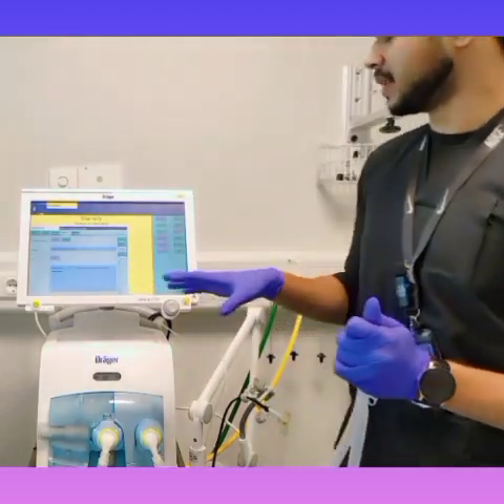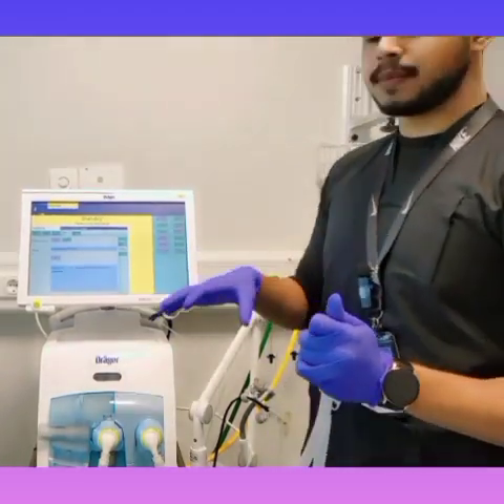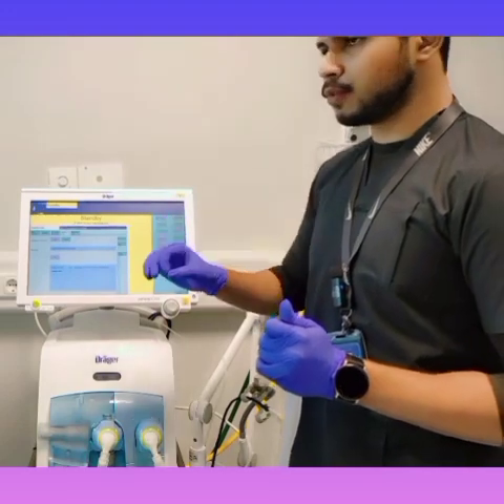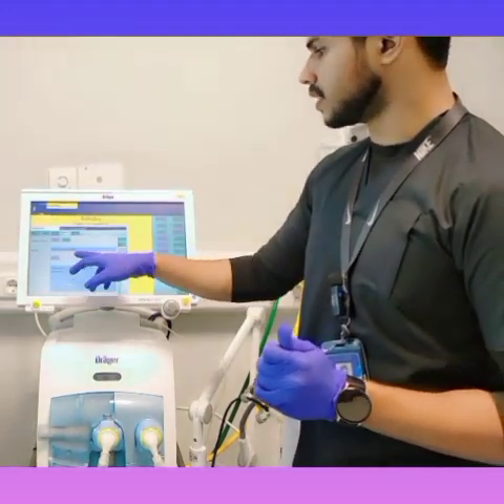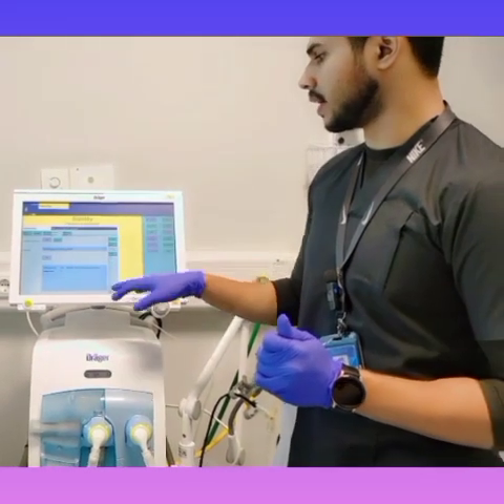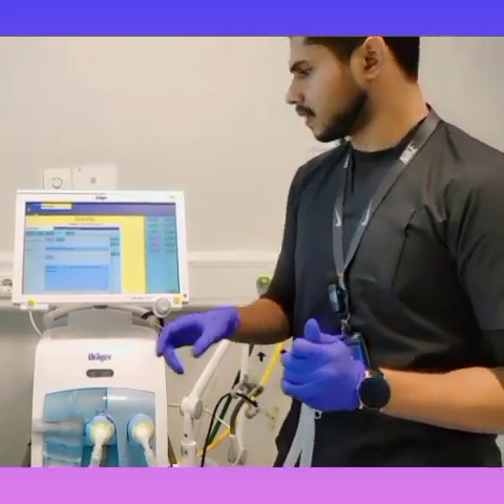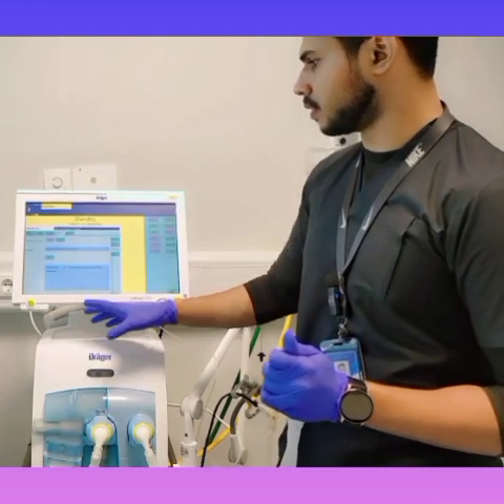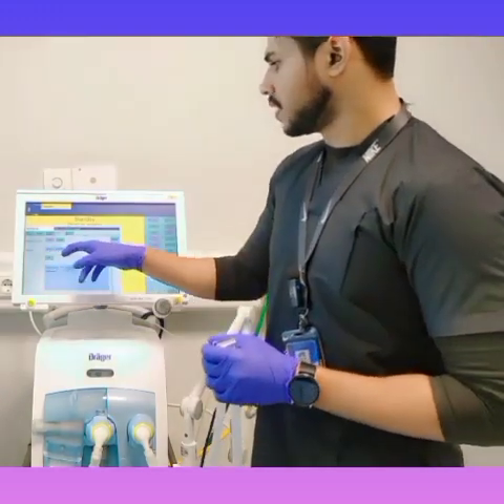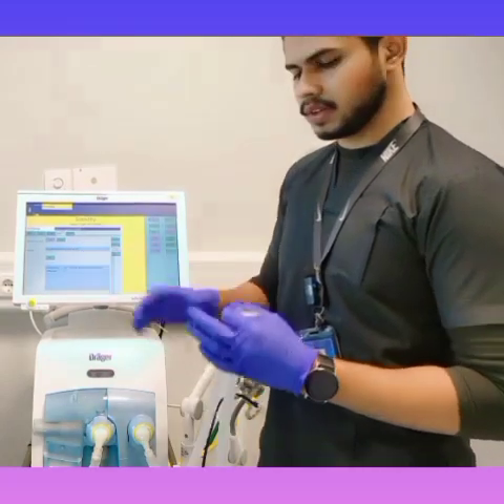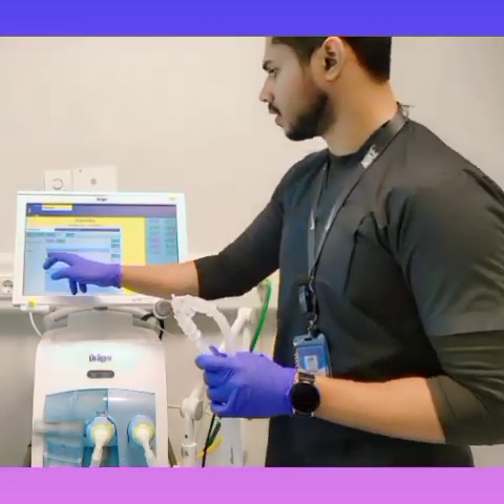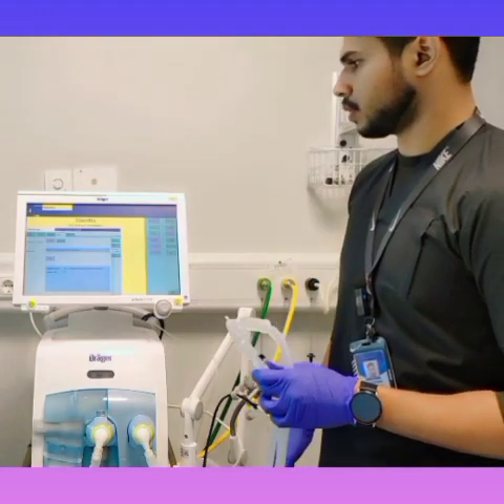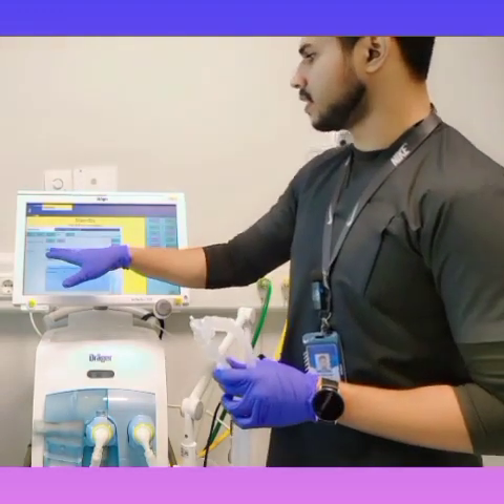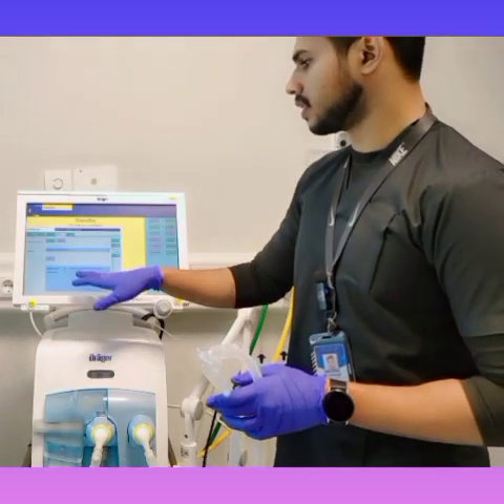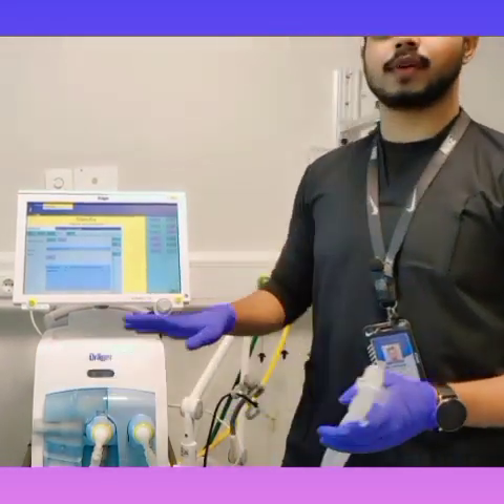So the leakage determination test is in progress. Remember, if you want to pass this test, your leakage should be less than 300 ml per minute at the pressure of 60 mbar. Okay, here you can see it is 14.2. Now open patient connection port, confirm with OK. Now you can leave it out. Okay, as you can see, breathing circuit check is finished now and your leakage is less than 300. Now your device is fully calibrated and ready to use.